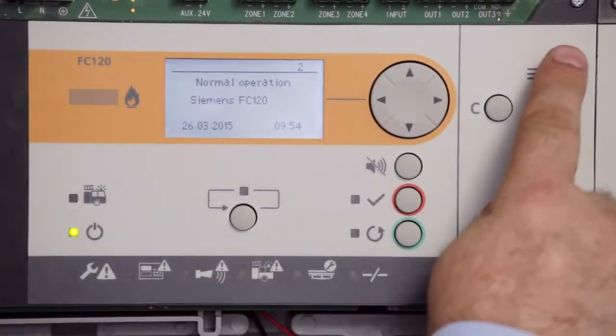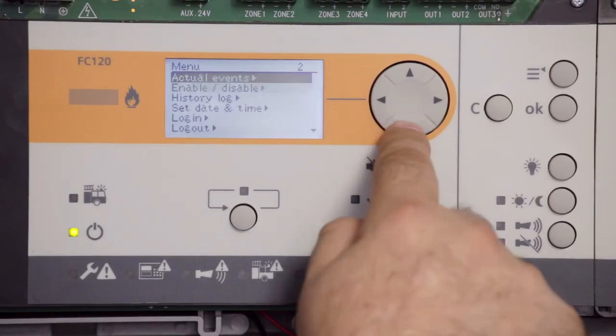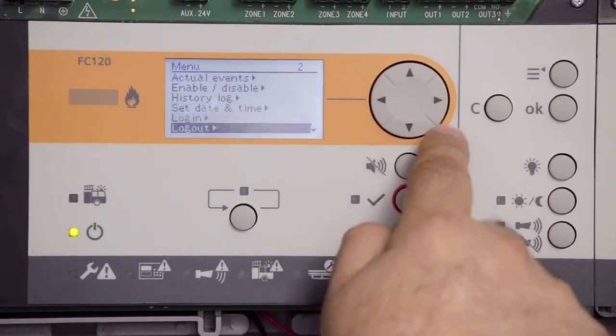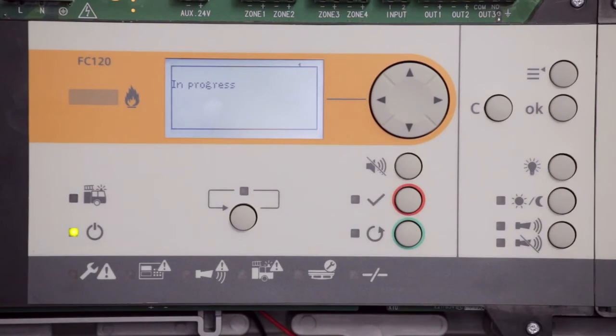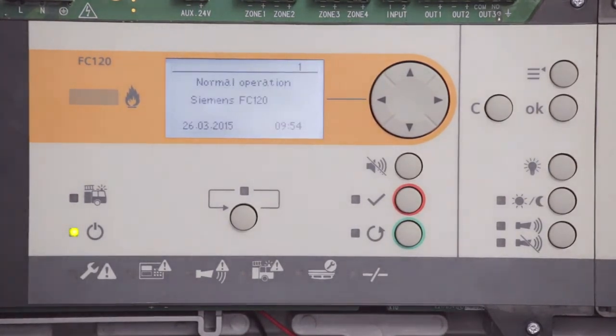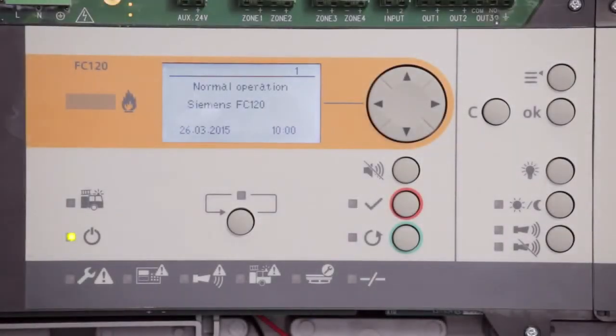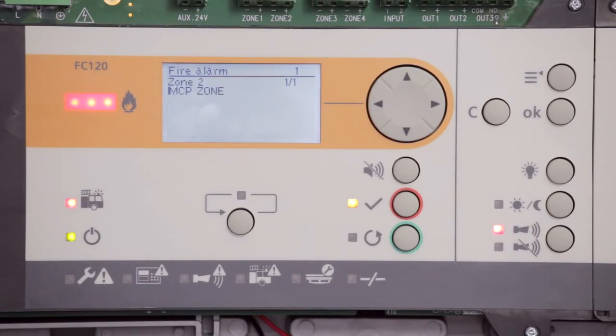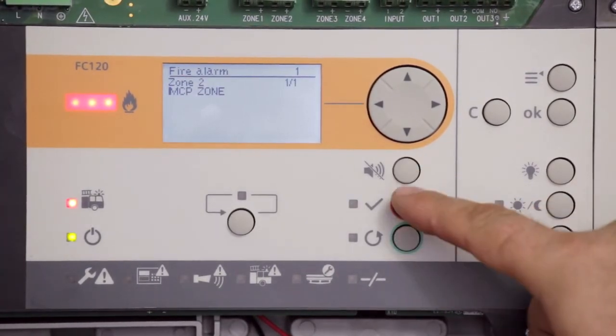Now, let's see how to manually log out to access level 1. The panel automatically logs out if no action is taken within 2 minutes. Push the menu button. Select Logout and confirm with OK. The panel is successfully logged out to the previous access level. Disable all off statuses. If possible, perform a test alarm on a manual call point and check all activations.